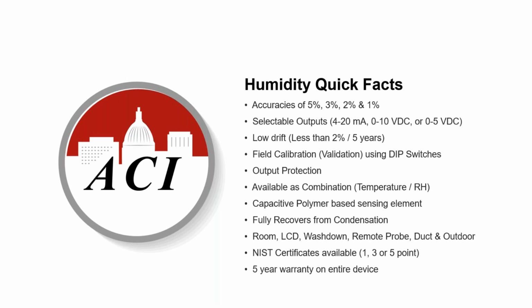We spec some of the lowest drift in the industry, less than 2% over 5 years, which is pretty darn good, pretty tight. We are the only one that offers field calibration or validation right on the circuit board using the dip switches on our sensor itself. All of our other competitors do not have this function or feature. You would actually have to do the offset back at the control system, and depending where that is in the application or the space, or in the building, that could be difficult at times. So keep that in mind. Obviously output protected, like I'd mentioned, and it is available in a combination unit.